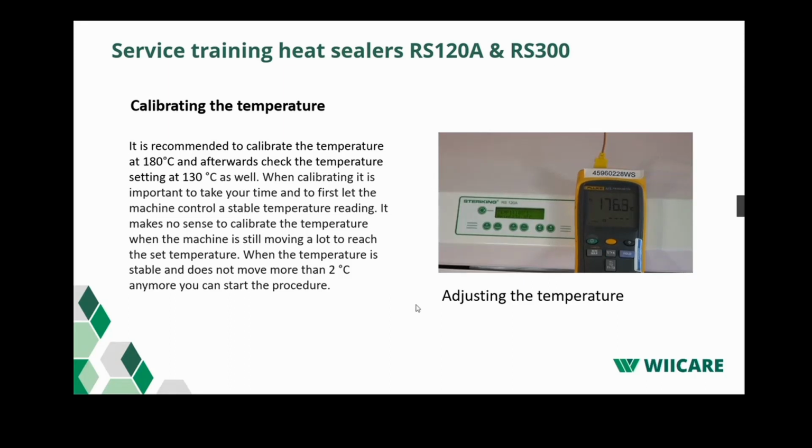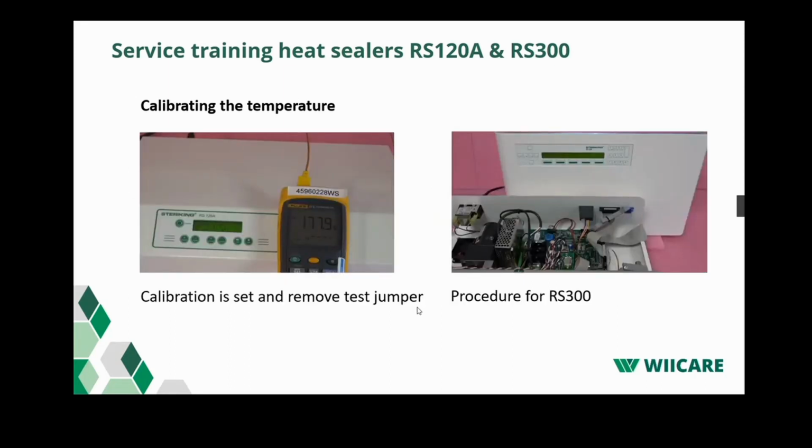Okay, we move on to the next video. This video shows how to proceed when the calibration is done. And then in the following video, we also have a video of the RS300. Basically all the videos you've seen in the presentation for changing the heating elements, changing the Teflon, the pulleys, apply for both types of heat sealers, so the RS120A and the RS300. Only for the calibration of the temperature and the pressure, there is a slight difference between the two machines.